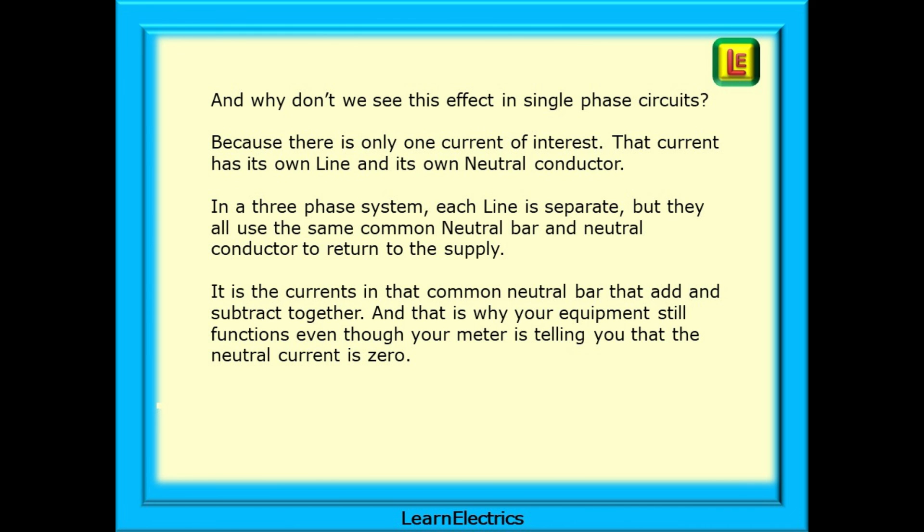And why don't we see this effect in single-phase circuits? That is because there is only one current of interest to us. That single current, that single phase, has its own line and its own neutral conductors. In a three-phase system, each line is separate, but they all use the same common neutral conductors. It is the current in that common neutral bar that add and subtract together. And that is why your equipment still functions, even though your meter is telling you that the neutral current is zero. The current is there, but it is being balanced out by Kirchhoff's law.